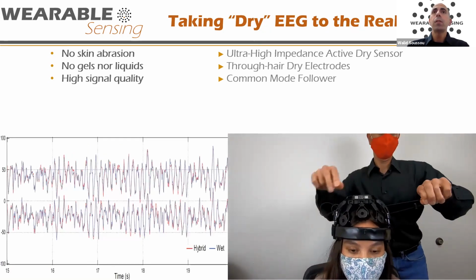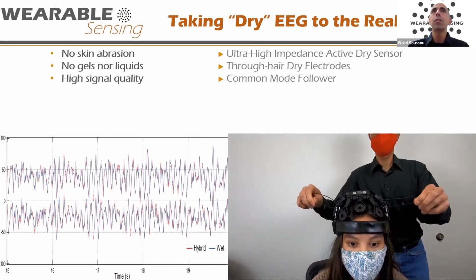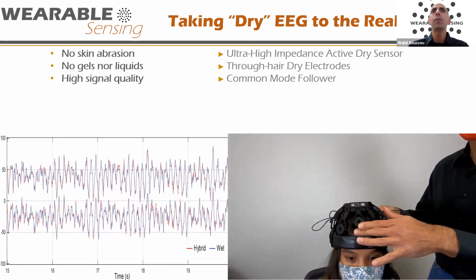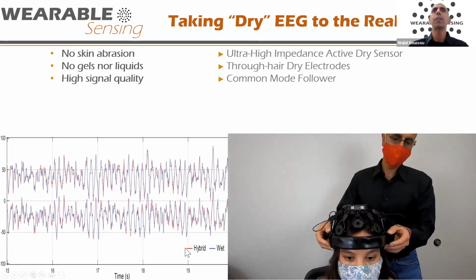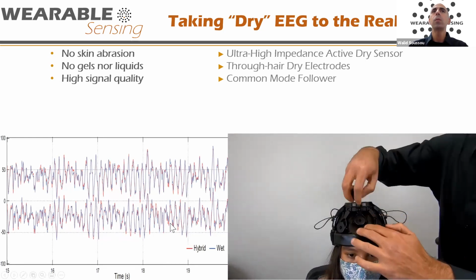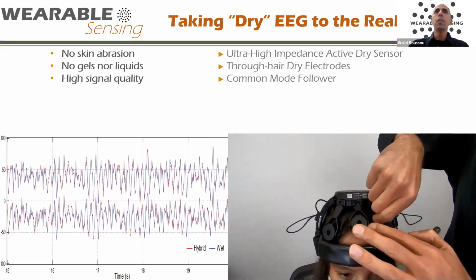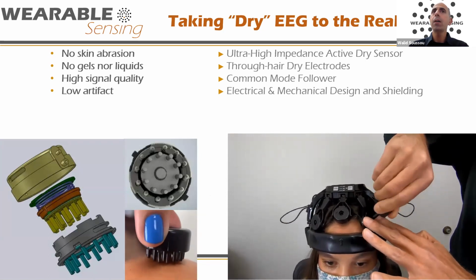The sponsors were, of course, very cautious and asked for us to validate that we were getting the same signal quality as we would get from a conventional wet electrode. Here you're seeing a recording of alpha activity simultaneously from our hybrid resistive capacitive dry electrode and the wet electrode. So you can see these traces here. We're getting better than 90% correlations, really good matching of the morphology.